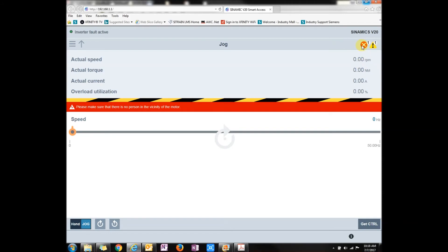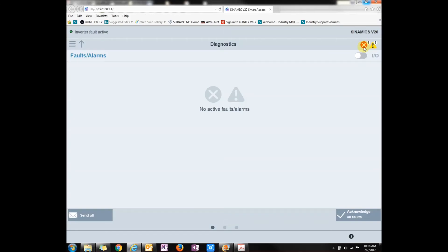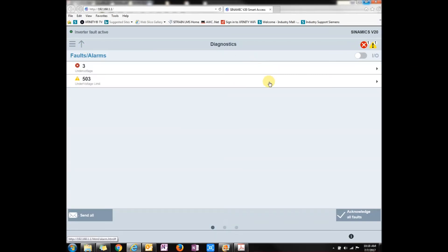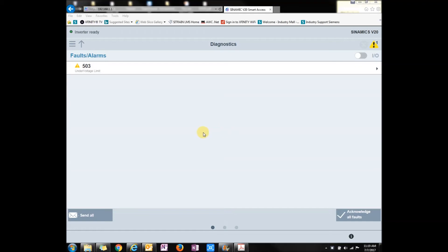Now I can see there's another fault that came up. I can just click on that, and it brings me straight to my fault screen. Under voltage, under voltage. It's because of my line. This is the diagnostic screen, which I just got to go to. While we're on the diagnostic screen, let's look at a couple things.